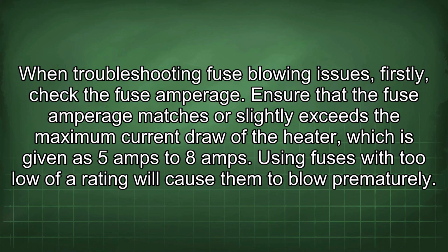When troubleshooting fuse blowing issues, firstly check the fuse amperage. Ensure that the fuse amperage matches or slightly exceeds the maximum current draw of the heater, which is given as 5 amps to 8 amps. Using fuses with too low of a rating will cause them to blow prematurely.